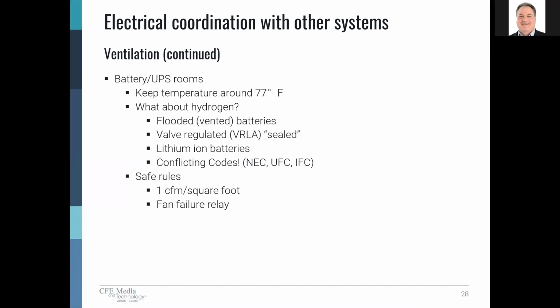But in general, the sealed batteries are very temperature sensitive. Anything above 77 degrees Fahrenheit, their life starts to reduce significantly. So that's the value you want to use with your mechanical engineer to keep that room cool. Lithium-ion batteries don't have that type of temperature limitation, but keep in mind that even if you specify lithium-ion batteries now, the owner may change them to something else in the future if they're on a tight budget. So consider the cooling carefully.